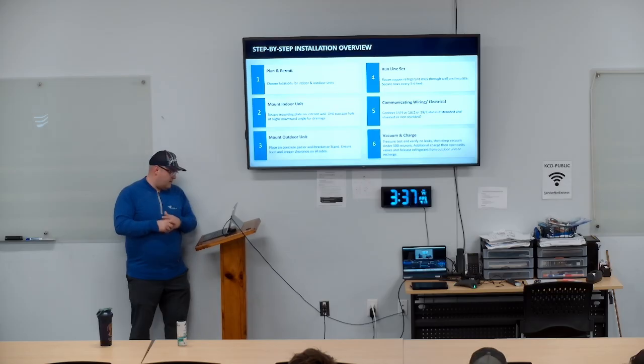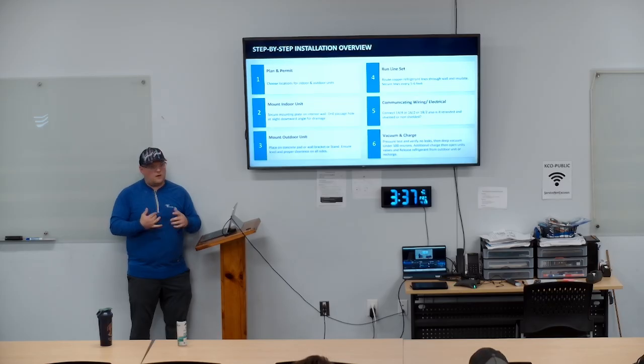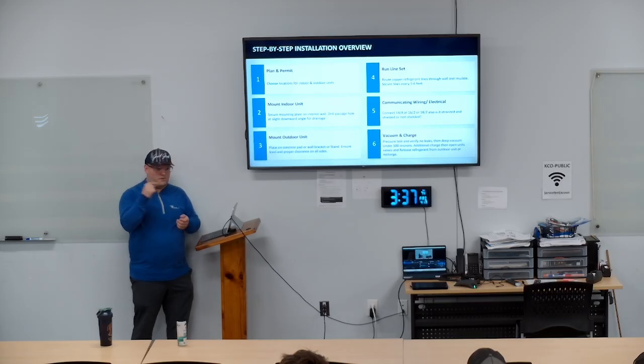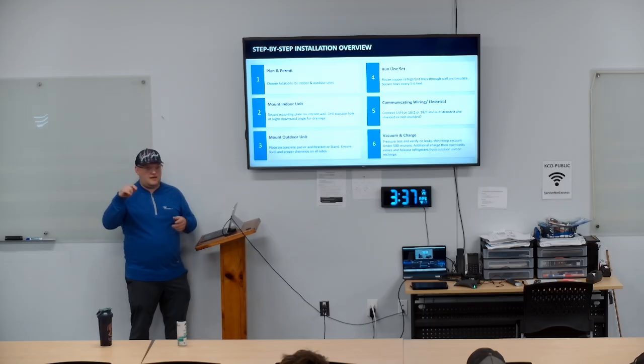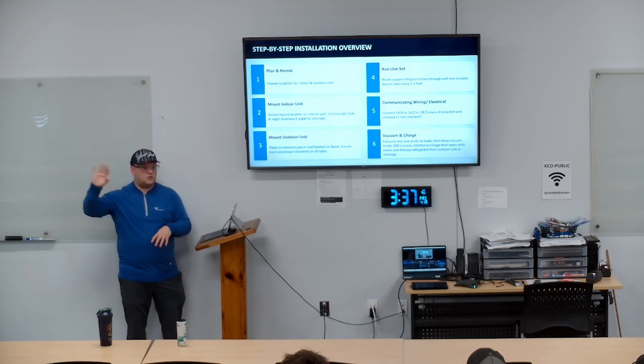Again, so think about that. Vacuuming, charging, pressure testing. A lot of you already know microns under 500, got to hold. Again, it's all in the installation manual, so they want pressure test. We like a 24-hour pressure test. So that's planning, right? So if I know I'm going to be there 2 days, the first thing I'm going to do is I'm going to get there. I'm going to hook up my line set both sides. I'm going to pump it with pressure, and I'm going to take bubbles. And if it's flared on either side, I'm going to check flares. Okay, it's not leaking. I'm good. I'm going to leave it now till tomorrow.